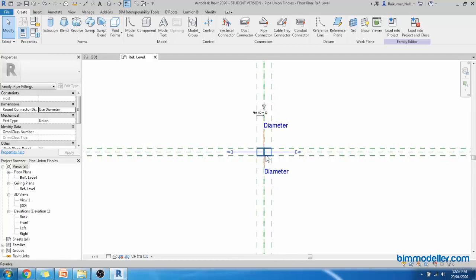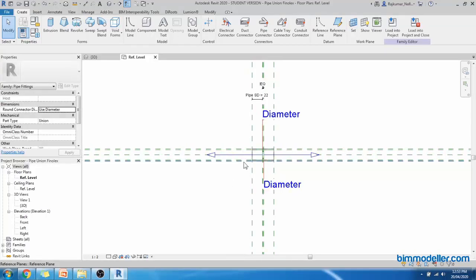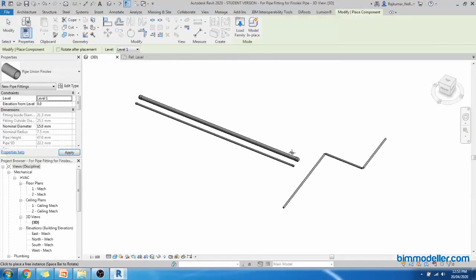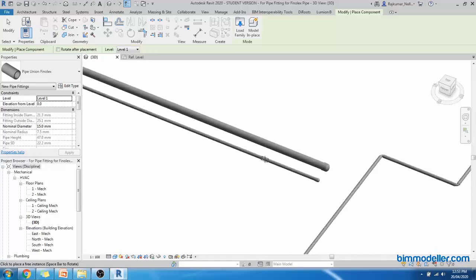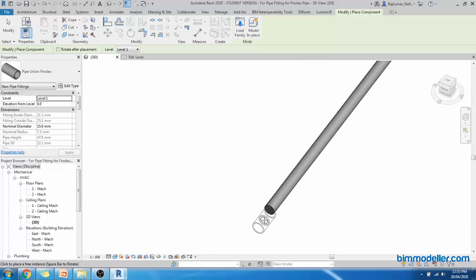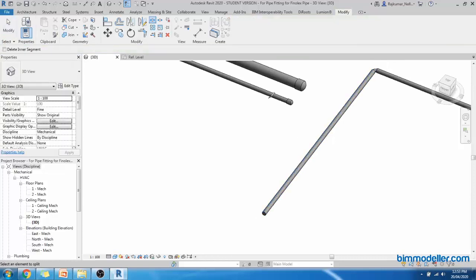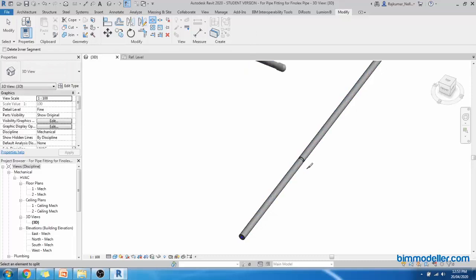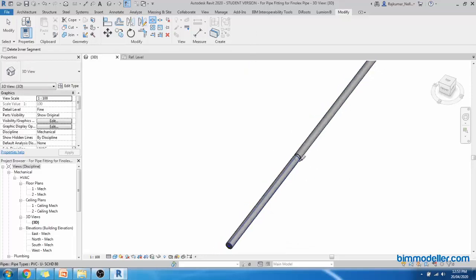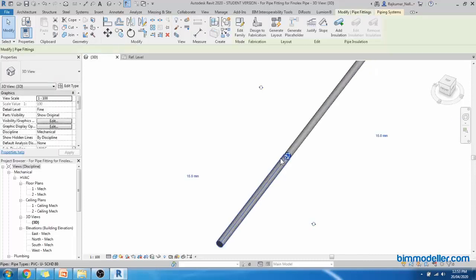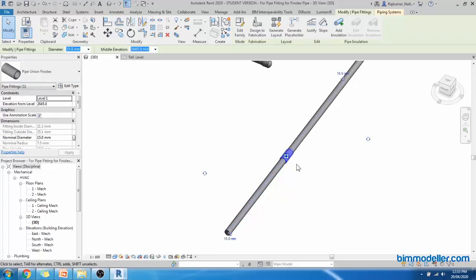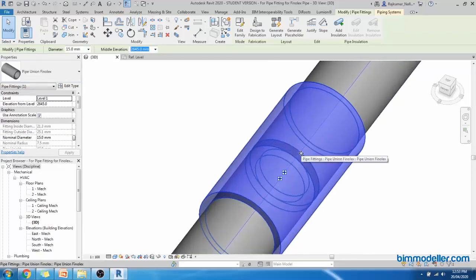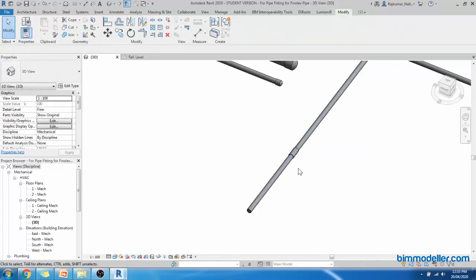Save the family. I hope everything is good. We have to create the symbol only depending on the symbol. We can save the family. Let's test it inside the project. Load into project. If I come near pipe to pipe, see that it is aligning. It's perfect. If I use split command, if I click the pipe, it automatically creates the pipe fitting which is assigned with the pipe settings. Now if I change this to our union, Finolex pipe fitting, it should accept it. Finolex pipe fitting, it goes still inside. OK, so assigning it works.